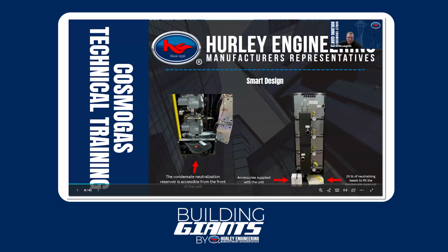Well, CosmoGas includes their neutralizing canister in the boiler. So it's already elevated to the point it needs to be. You don't have to elevate the pad any further. You can set this on any surface that you need. You need to keep it level. But then all you need is a small amount of elevation change so that you can drain from that neutralizing canister to your floor drain or to your pump or whatever you're going to.